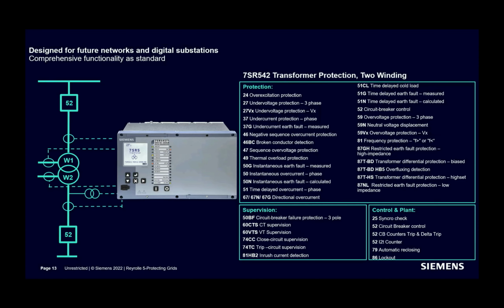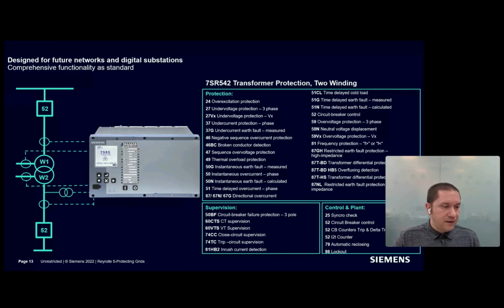And 24 overexcitation protection detects excess core flux density, which causes overheating. And again, our frequency protections here on the substation incomer transformer can be used to initiate load shedding of the connected load, especially with 81R frequency rate of change functionality. This ability can complete a system-wide load shedding application. As expected, 7SR5 can control the 2 circuit breakers on both sides. And of course, the 25 synchro check function can also be applied, for example, on the downstream circuit breaker.